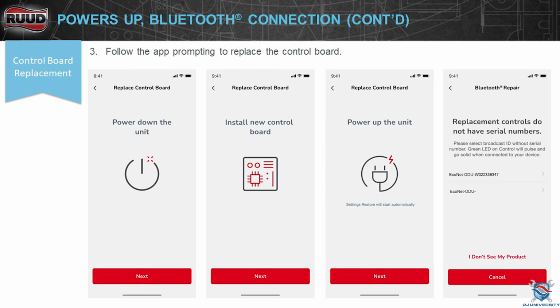Easiest way, connect to it. Once you've connected to it, it's going to tell you to power down, install the new control board, and power up the unit. If you see "replacement controls do not have serial numbers," continue through that, okay? Because that is true, it does not have a serial number. So once you hit cancel, there will be a continue button on the next screen. Hit that continue button, and then it's going to populate your model and serial number on that next screen.